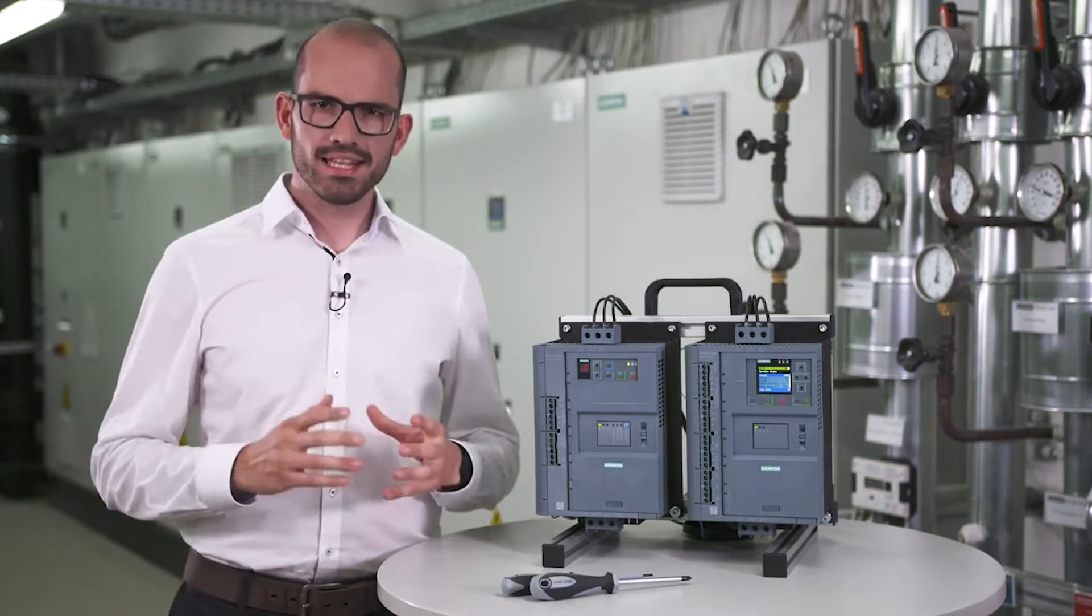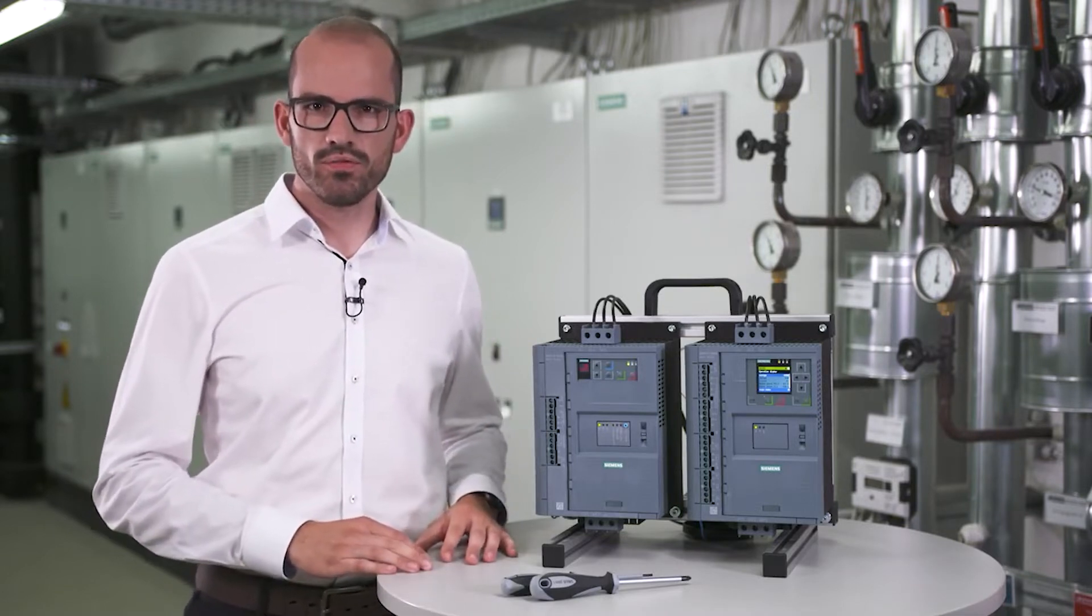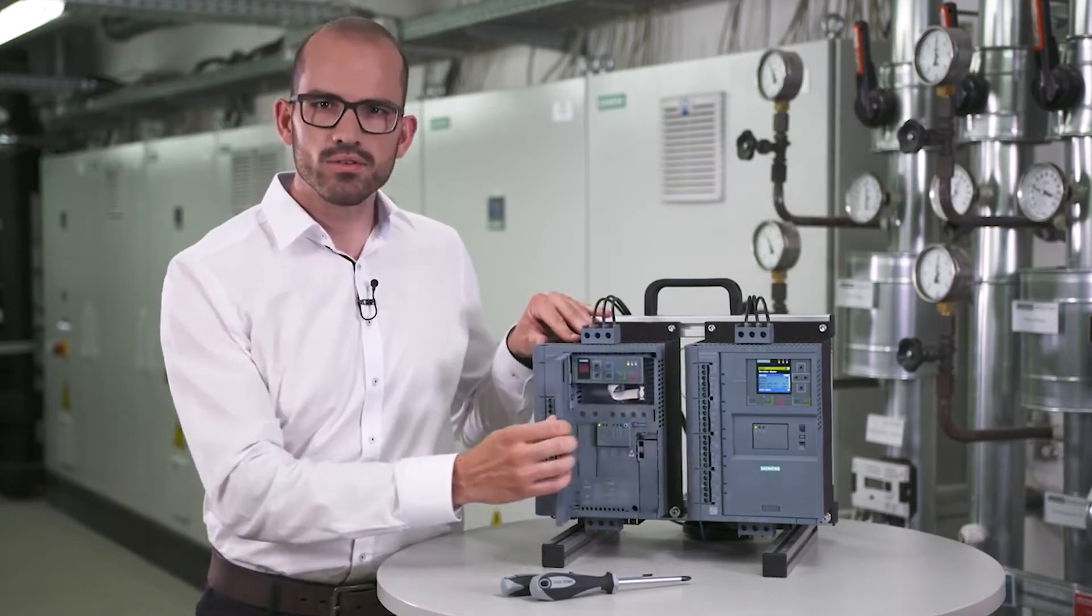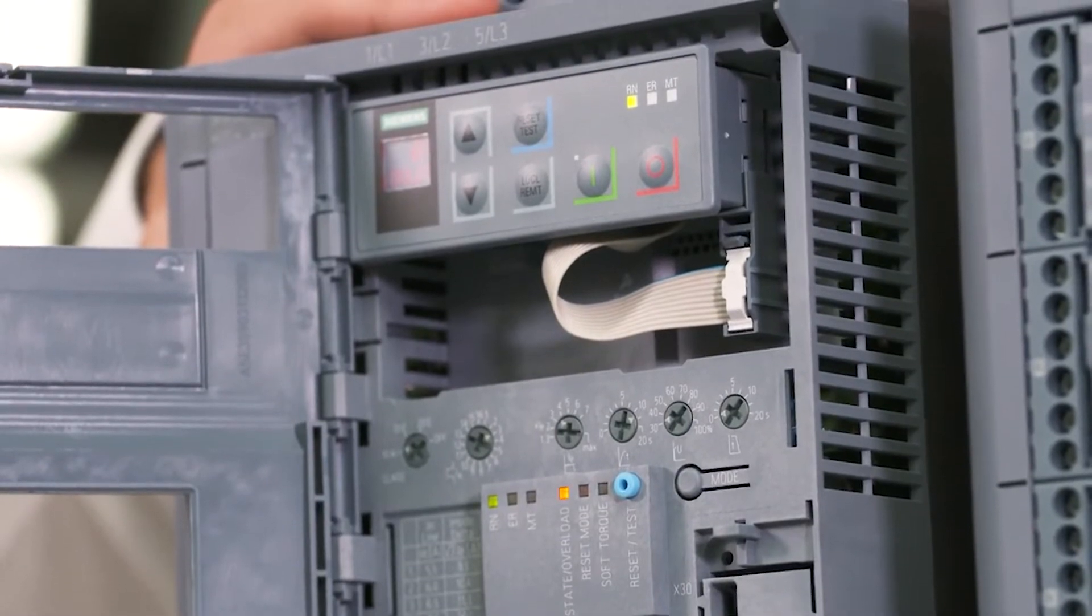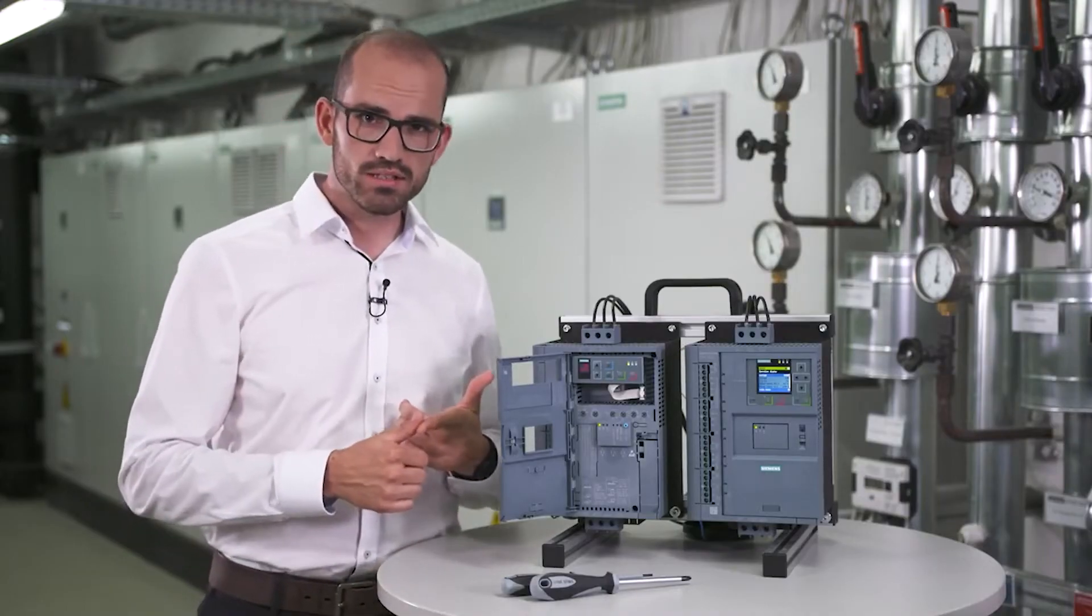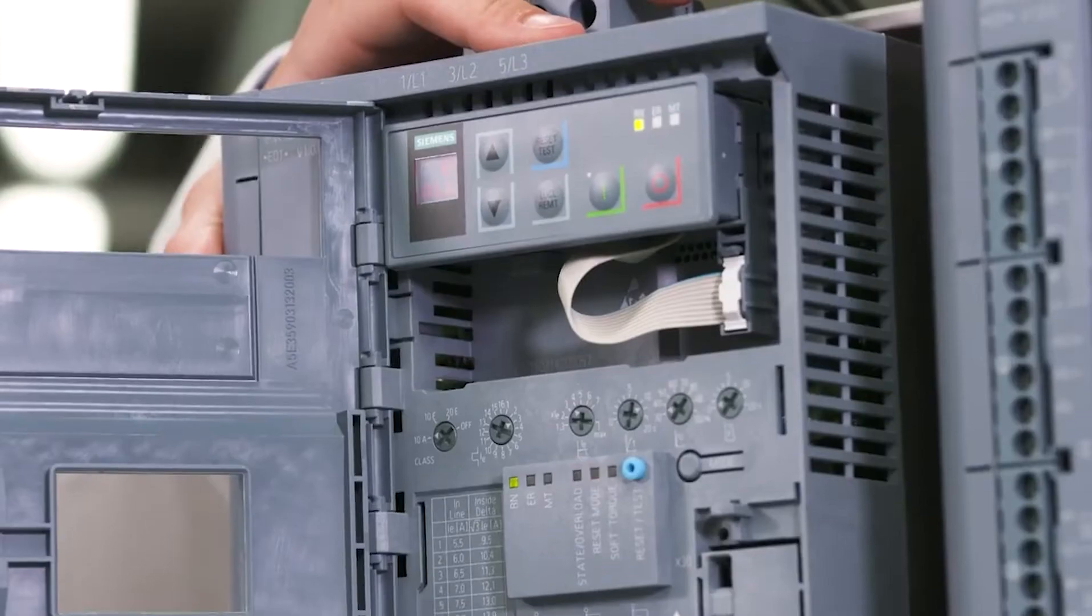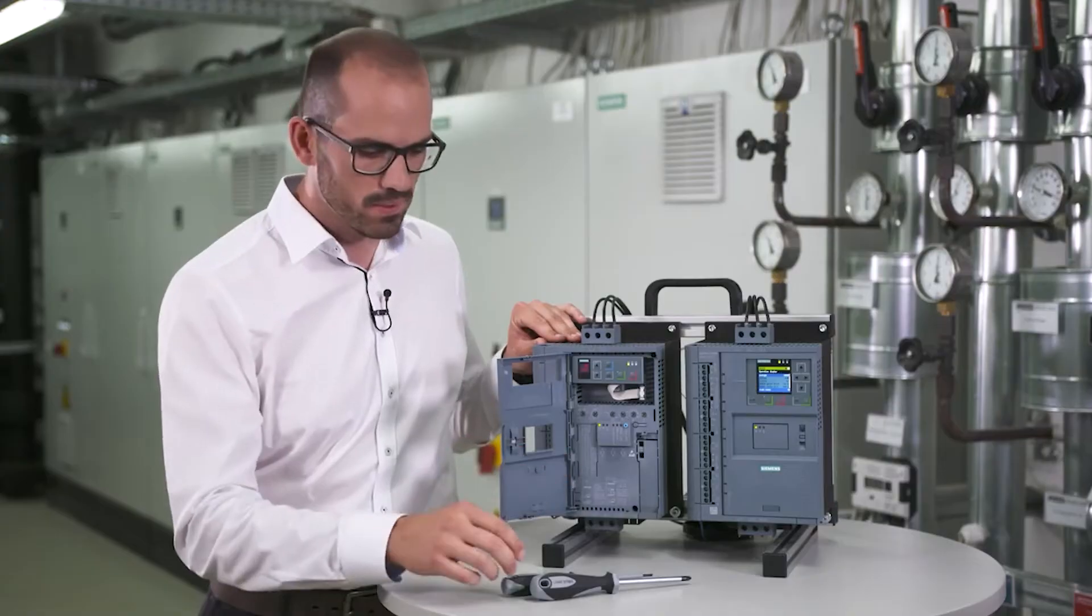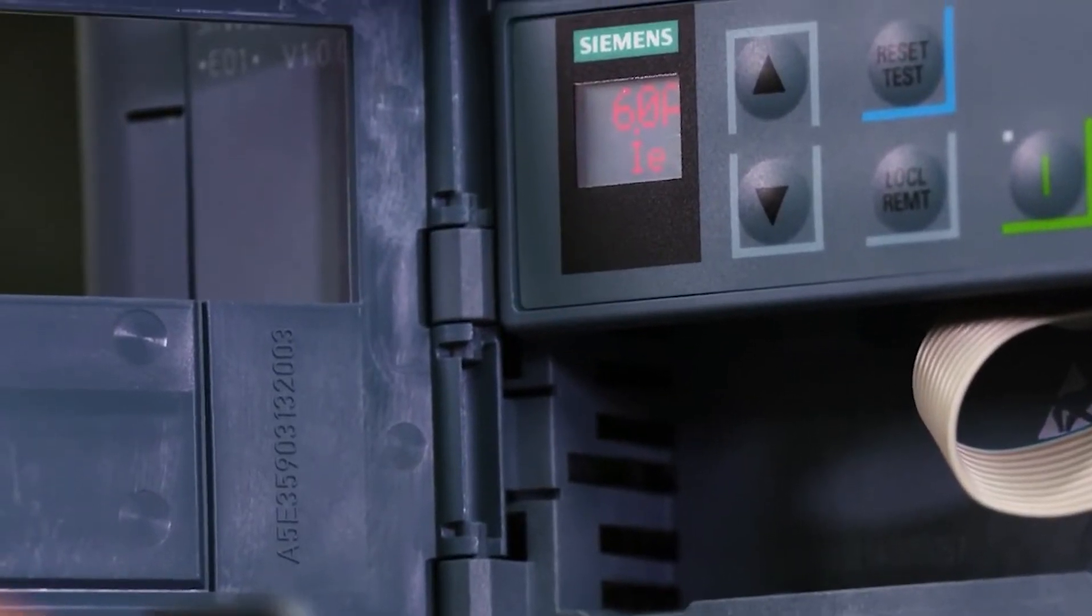Now let's have a look. How many parameters do you need to know for commissioning and how easy is it to set all of them? The six rotary knobs of the 3RW52 allow you to not forget any important parameters needed: motor rated current, current limitation factor, ramp up time, and so on. In combination with the HMI, all the values are displayed right away to make the commissioning really fast.